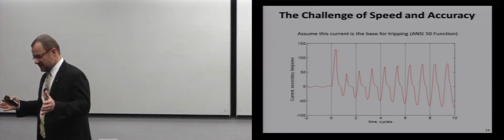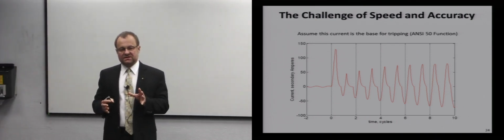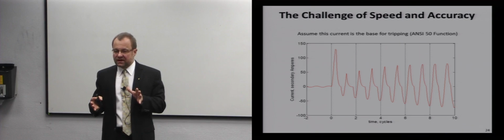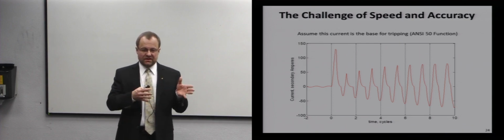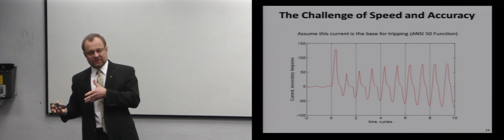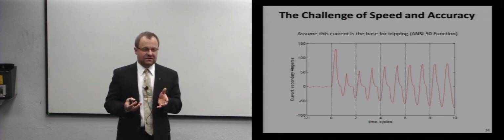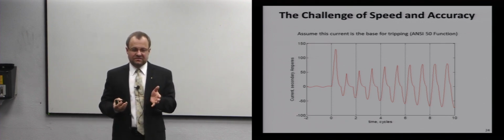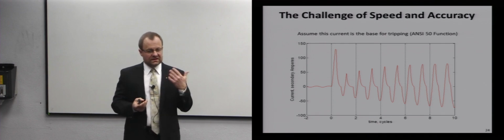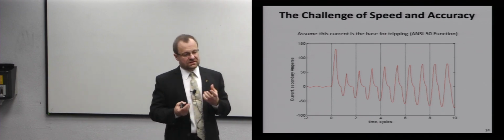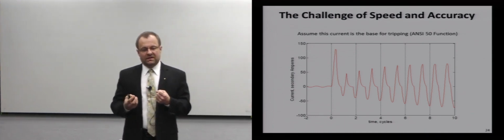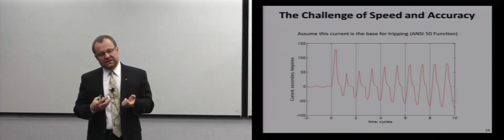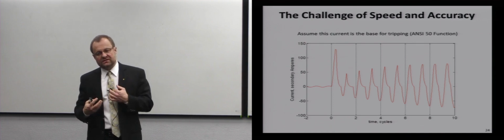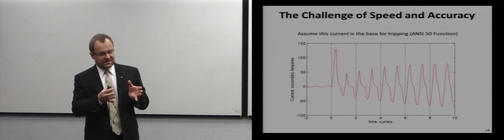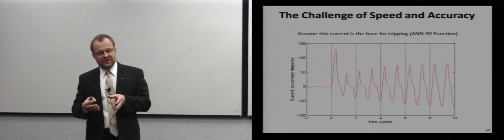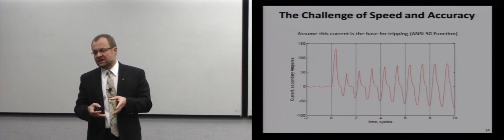So you have your hardware. Now, the beauty about microprocessor-based relays, and I hope you realize that, is that it's pretty generic. If I am a distance relay or a differential relay or a motor relay, do I need a different A to D converter? No. Do I need a different microprocessor? No. So there is a nice thing about microprocessor-based relays: the hardware becomes relatively generic. Now, for size, cost, and input-output requirement reasons, you will see different boxes. But what really differentiates those boxes is the software inside that they run.